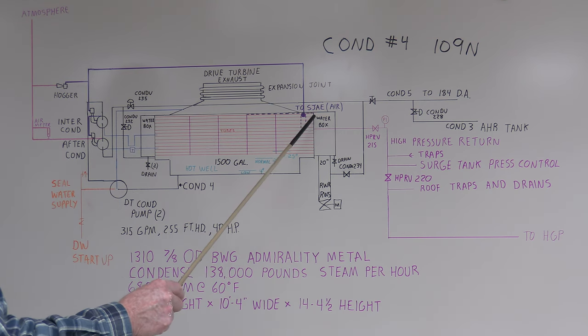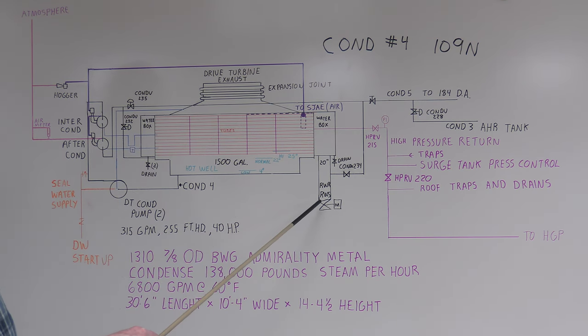The normal level in this was 22 inches, high level is 25 inches, low level is 4 inches. About 1,500 gallons at normal level. From here you had your suction line to your dump condenser condensate pump.